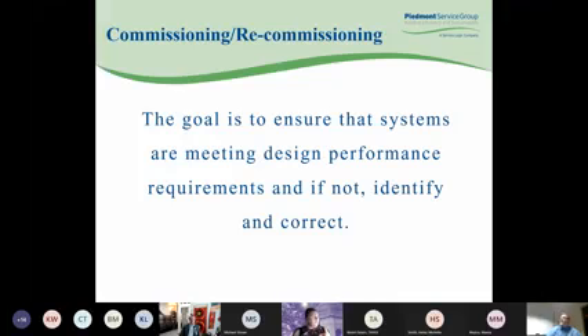Recommissioning a building's HVAC system is a basic and relatively inexpensive task that often has less than a 1-year payback. Basically, engineers make sure all equipment is at the right settings, that controls work properly, and that other equipment functions as designed. Measure and verify airflows and chilled water flows to make sure they're at design.